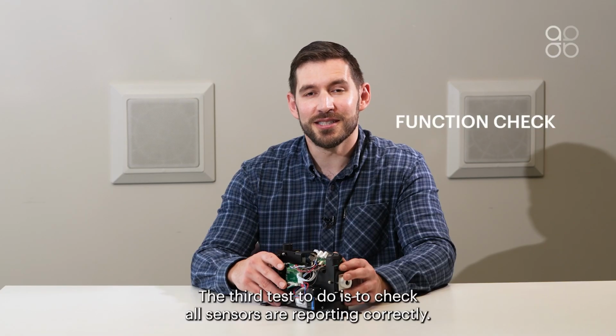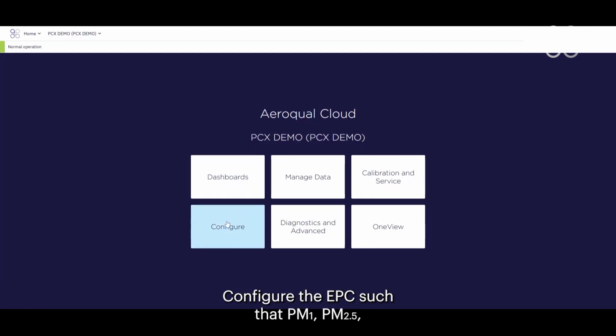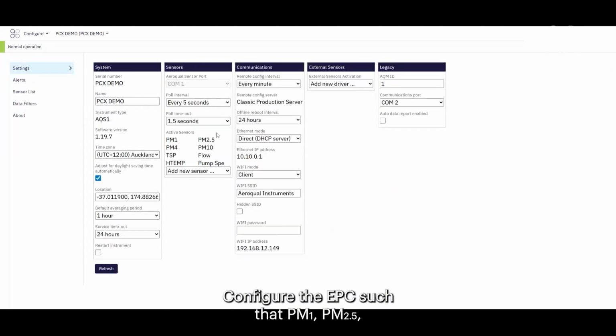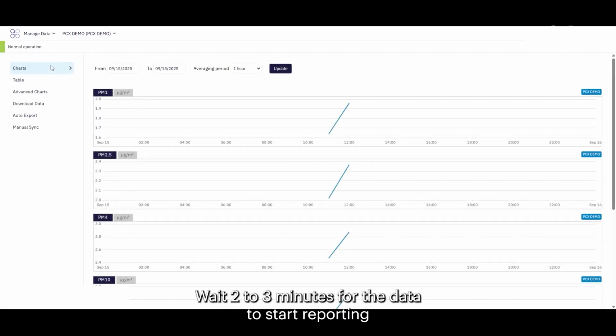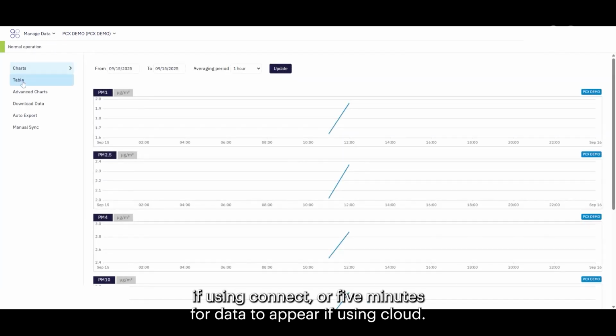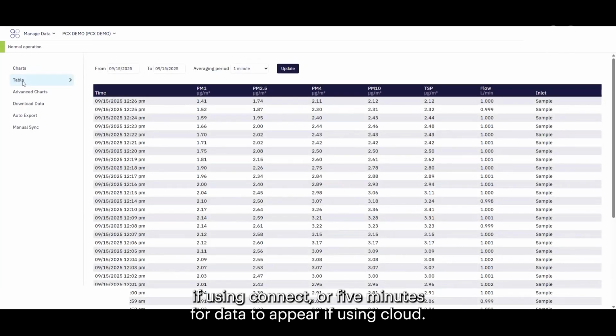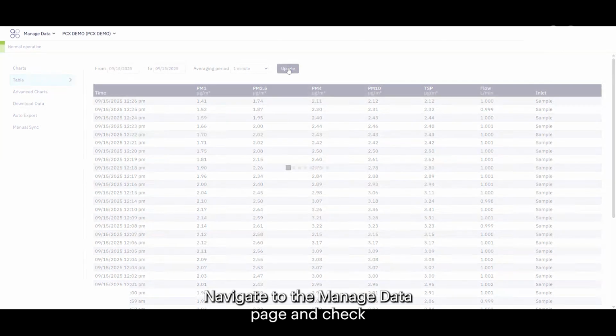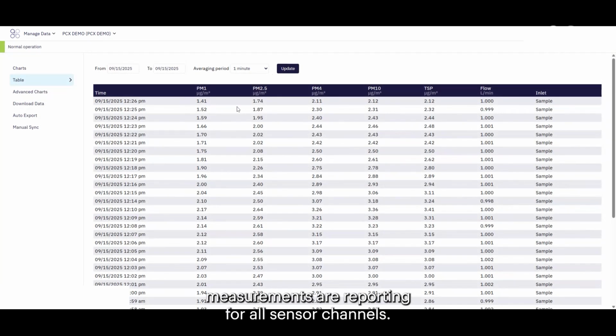The third test to do is to check all sensors are reporting correctly. Configure the EPC such that PM1, PM2.5, PM4, PM10, TSP, flow, pump speed, and H-temp are all reporting. Wait 2 to 3 minutes for the data to start reporting if using Connect, or 5 minutes for data to appear if using Cloud. Navigate to the Manage Data page and check measurements are reporting for all sensor channels. Check the status bar and confirm there are no channels reporting sensor failed, sensor offline, or sensor due for replacement.